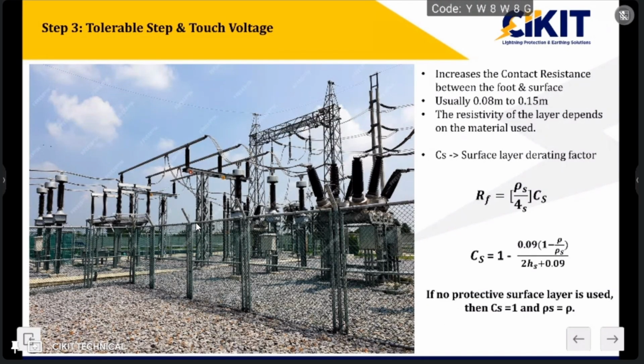If you closely observe the substation, we provide a layer of high resistive gravel on the substation. The ultimate reason for providing this gravel is to increase the contact resistance between the foot and the surface. For example, in the earlier case, some person is standing on the soil. In both the previous cases, for step and touch voltages, we are considering the resistance of the body alone. We are not considering the resistance of the shoes if they are wearing any, or the resistance of gloves. Let us consider this is the soil, and one person is standing here.